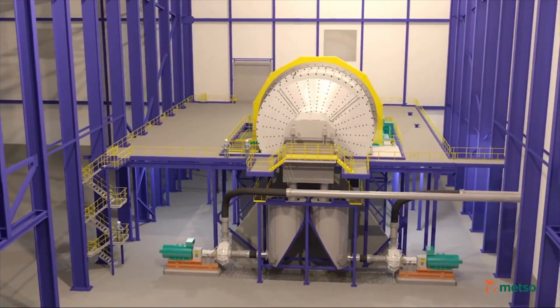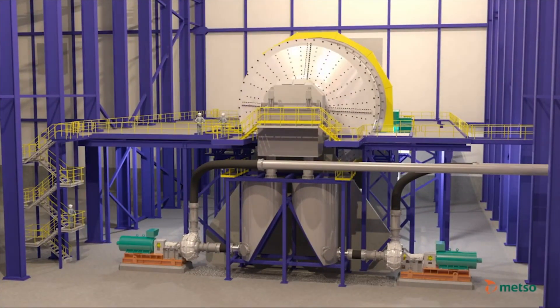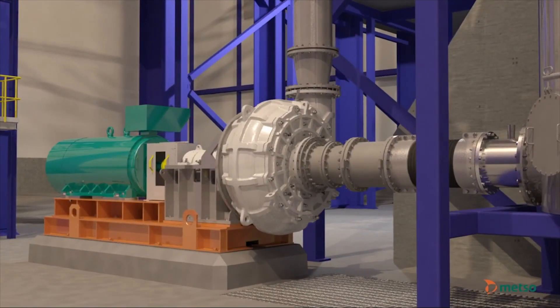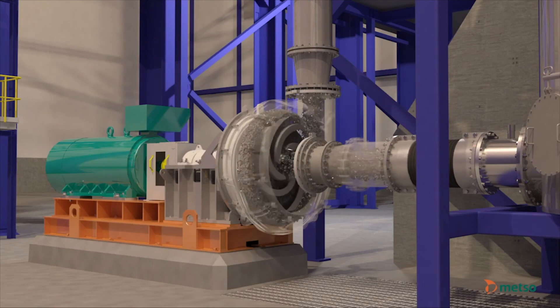Metso has a unique strategy on hydraulic designs. For coarse pumping in mill circuits and similar applications, we have a design strategy with lower entrance velocity, and the pump's best efficiency point is set at lower velocities — because with coarse particles you have to avoid high velocities. So for the tough pumps we have the BEP further to the left. On the tailings pump and later in the process, when you have finer particles, we have deliberately put the best efficiency point at higher velocities, which presents no limitation from a wear point of view. That's a key strategy of Metso hydraulic designs.